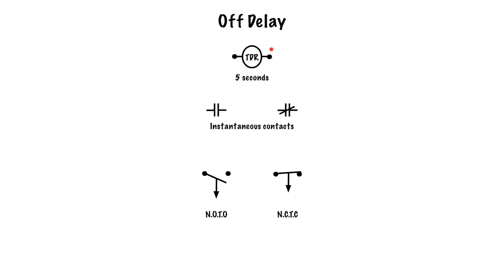Here we have a typical off delay. We have a TDR coil — time delay relay coil — with a timing function of five seconds. There are some normally open contacts and some normally closed contacts; those are instantaneous. The moment TDR energizes, these contacts close and these contacts open — it ignores the time. What doesn't ignore the time are the time contacts down here: a normally open time-to-open contact and a normally closed time-to-close contact.